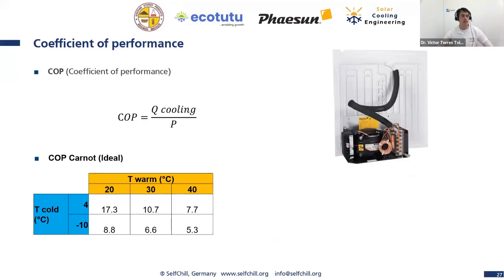You are pumping heat. If you have an ambient of 20 degrees and a cooling temperature of 4 degrees, so imagine a refrigerator in a room working, Carnot is telling us, and you can use the Carnot equation to get there, that your COP can get up to 17. Wow. I invest 1 kilowatt hour of electricity and get 17 kilowatt hours of cooling energy. Amazing, isn't it? What about at 40 degrees? It goes to 7.7, a little bit lower.